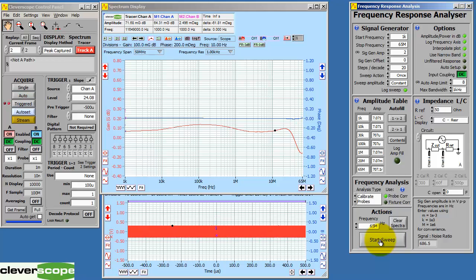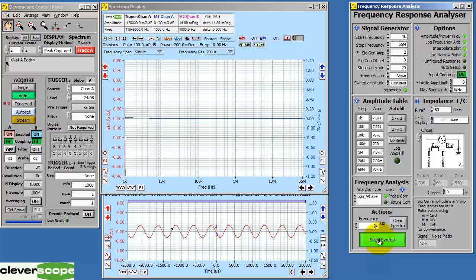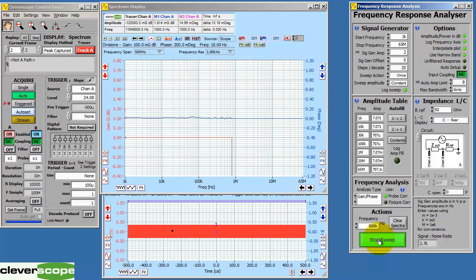Right, next we can check how the sweep has affected things. We change back to gain phase and do another start sweep. Now we should have the corrected version of the gain phase response for this jig and these cables. As you can see, the gain is now very flat and the phase response is very close to 0.